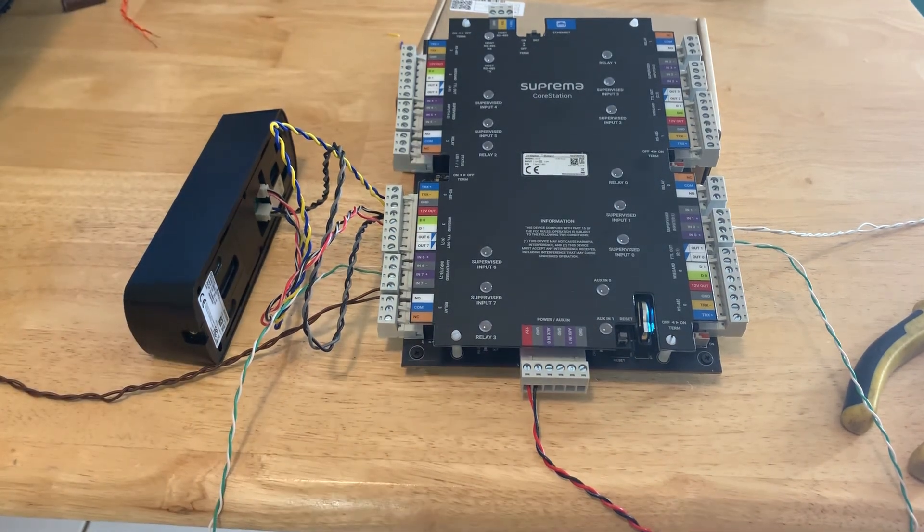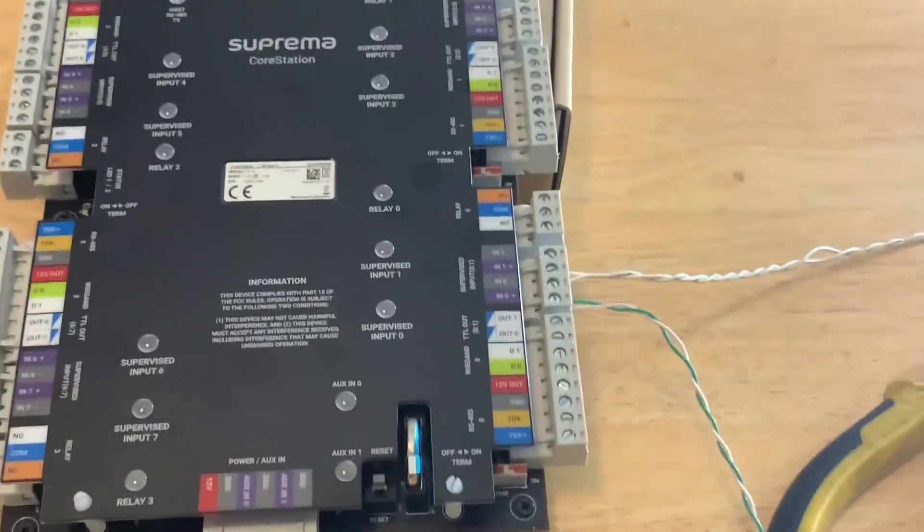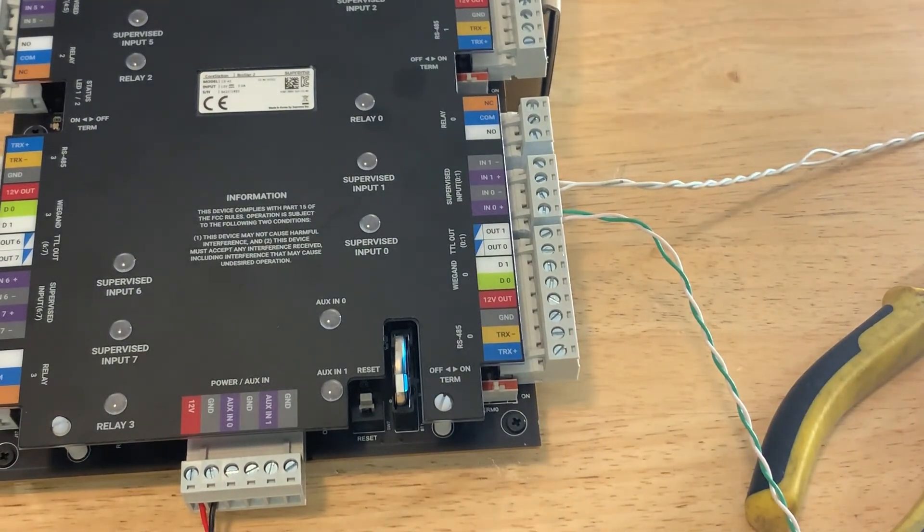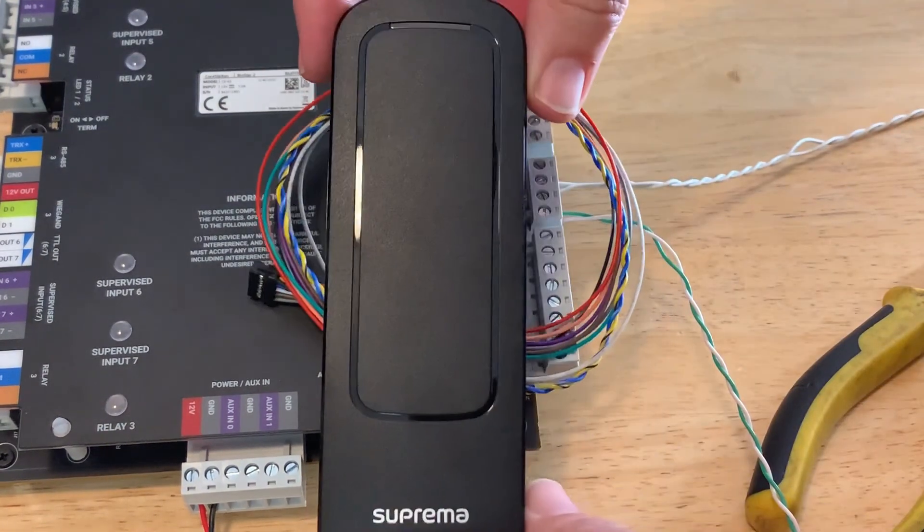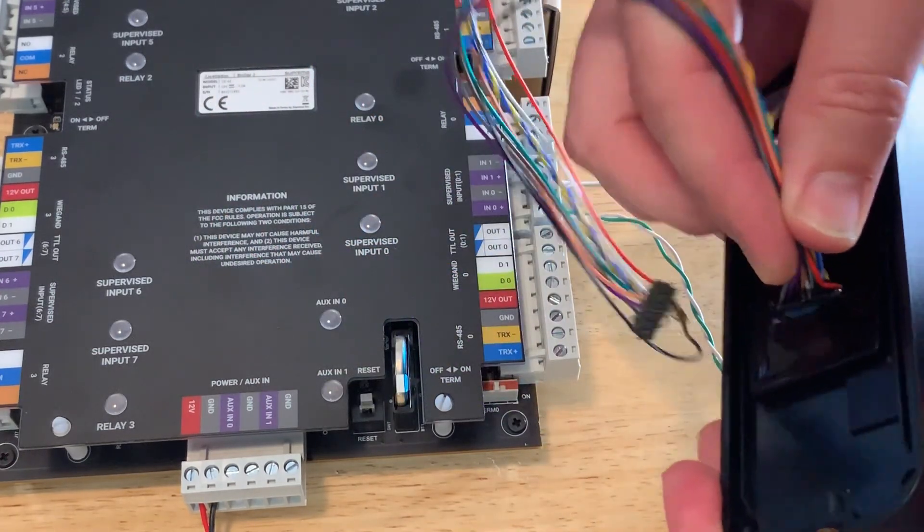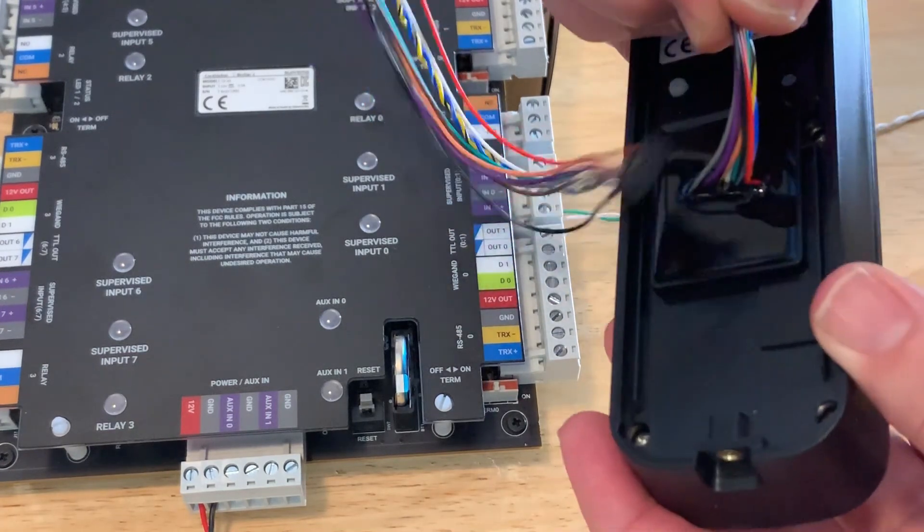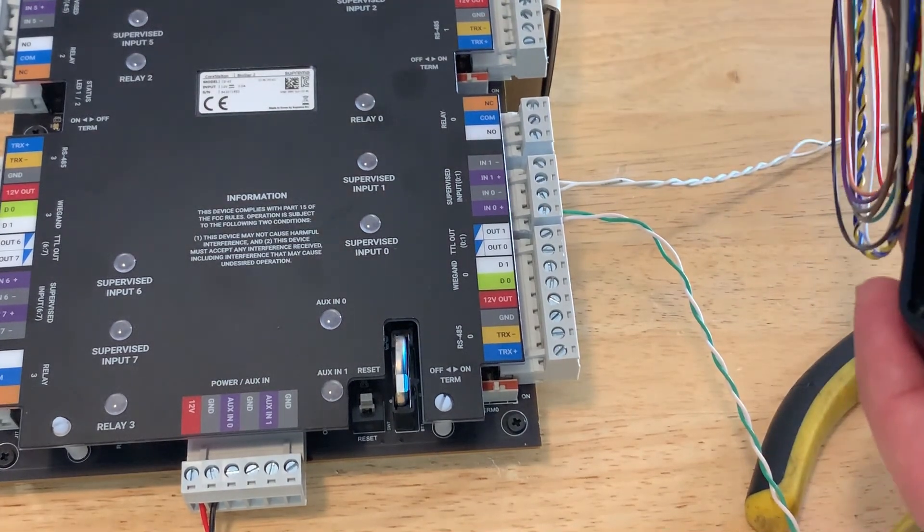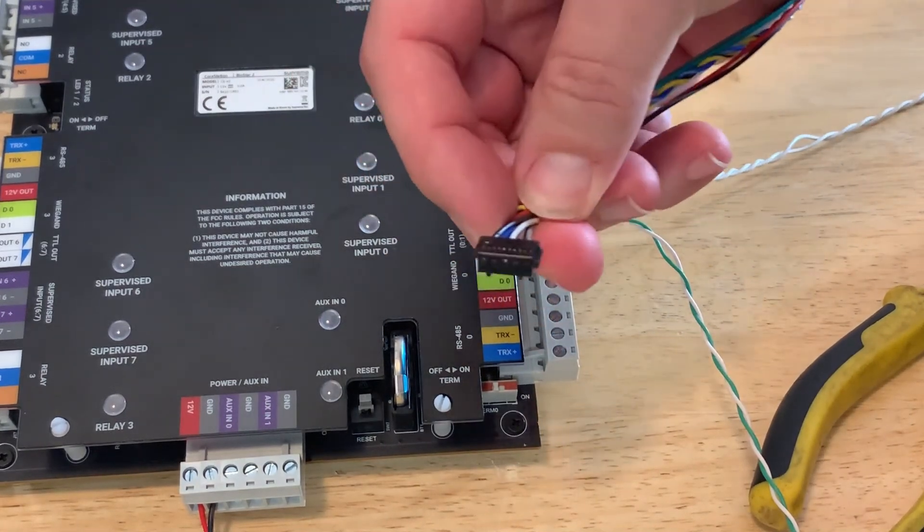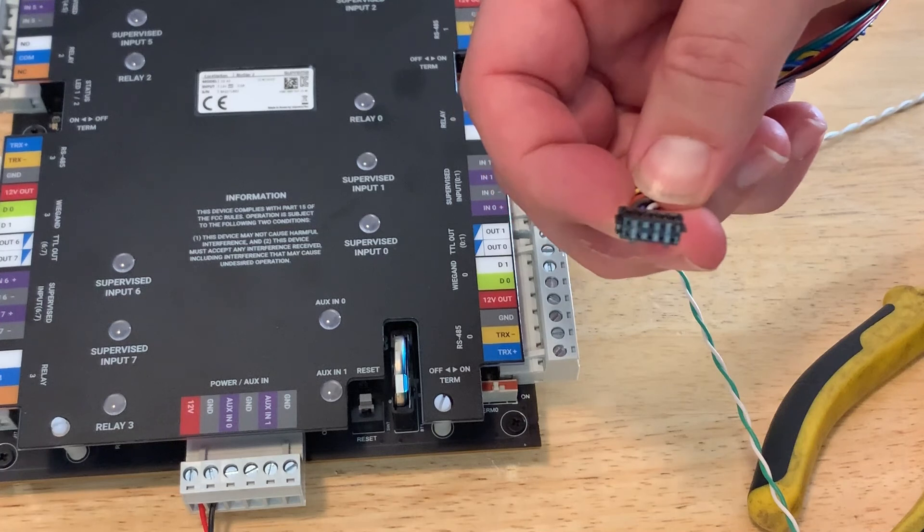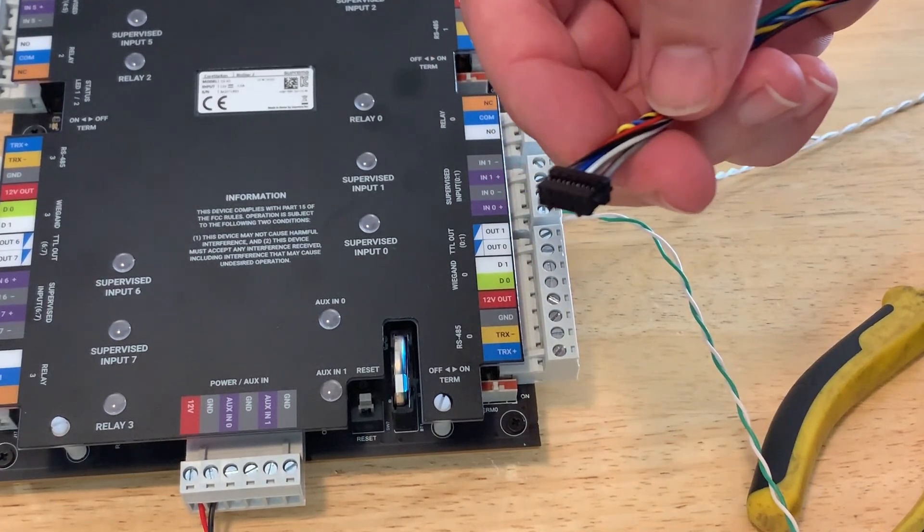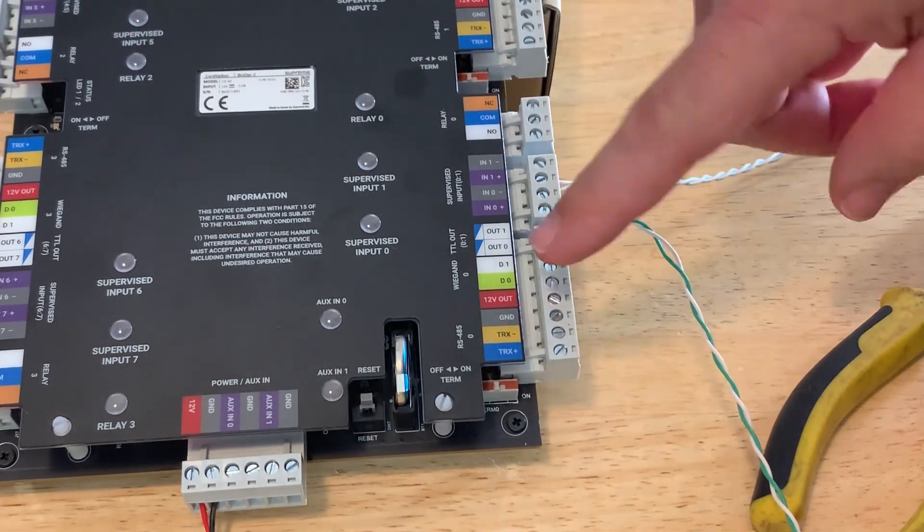I'll go ahead and wire in. I have an X-Pass D2 mullion style. I want to wire that into door port 0. And now this is the X-Pass D2 mullion. And now on the back of the unit it's sealed as far as the wires going in. So this can be outdoor rated. It can be mounted outdoors and so forth, while the R2 I just showed you has pigtails that can come out the back. It's for indoor use only. So with this pigtail here a lot of people ask do we have an adapter for that to connect to it? No we do not. So we just tell people cut it off completely or just cut off the wires you want to use. This application I'm going to be just using the 485 and power.